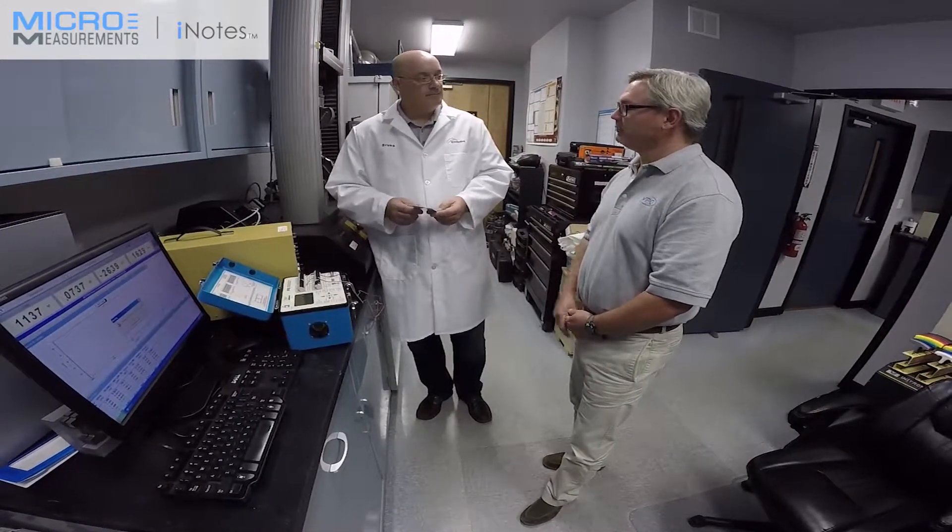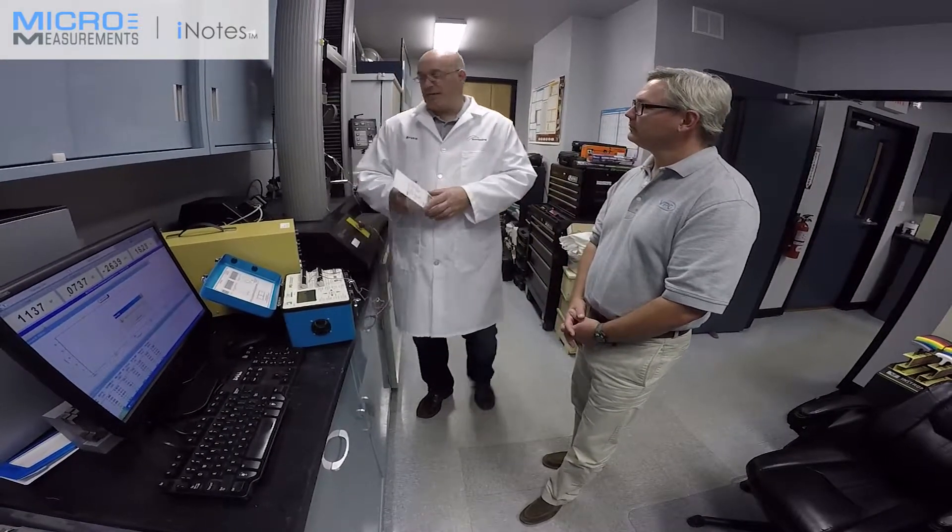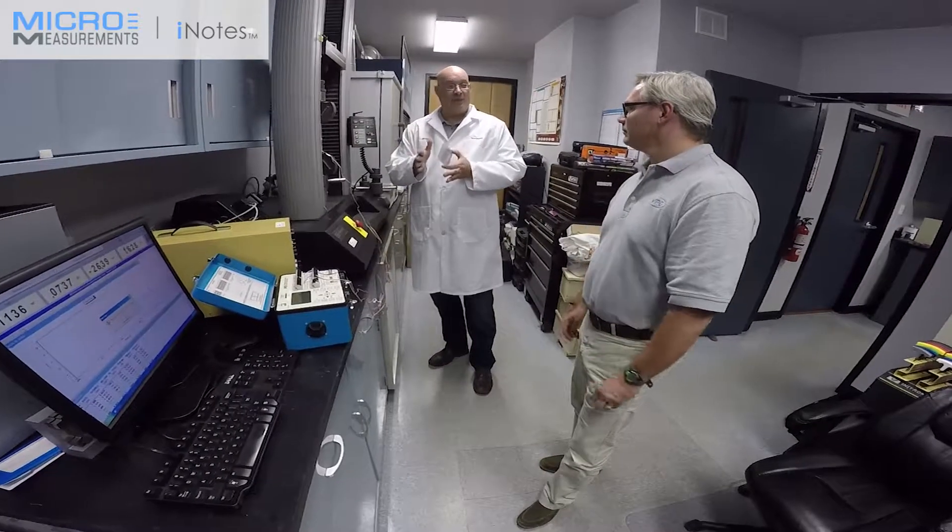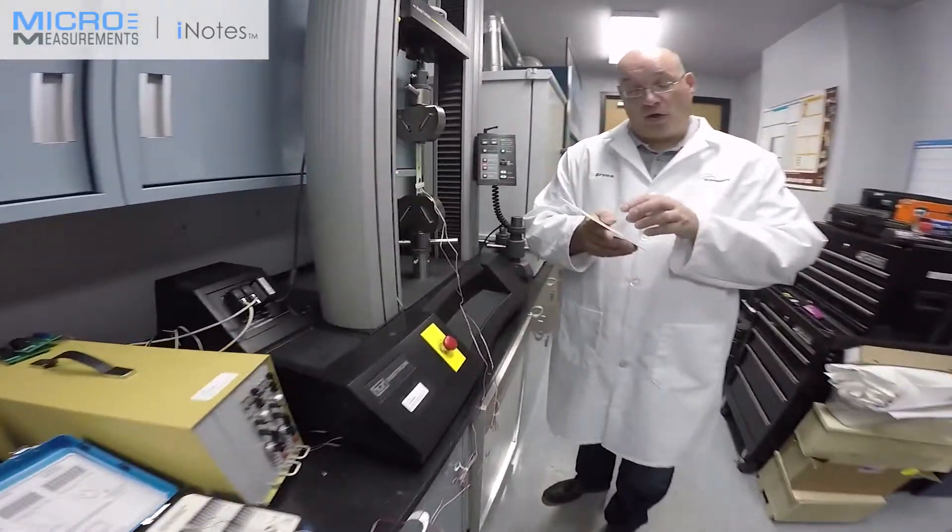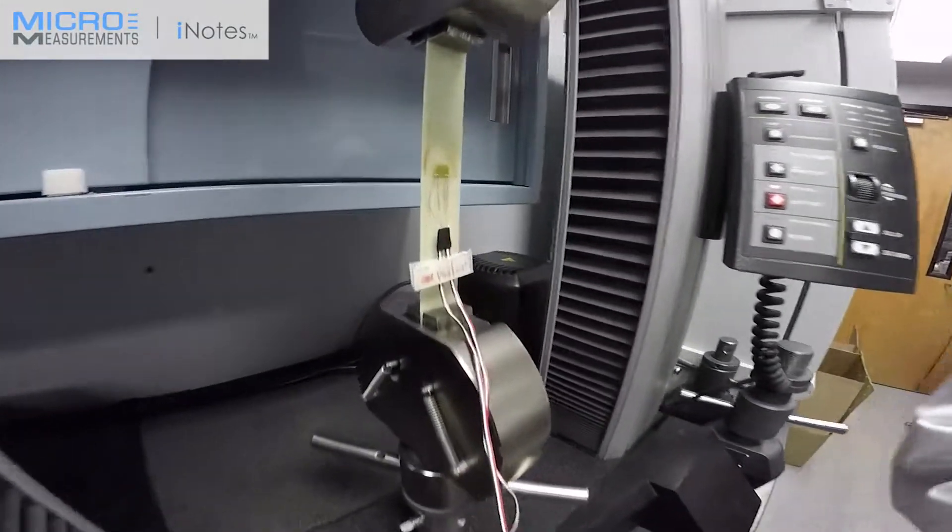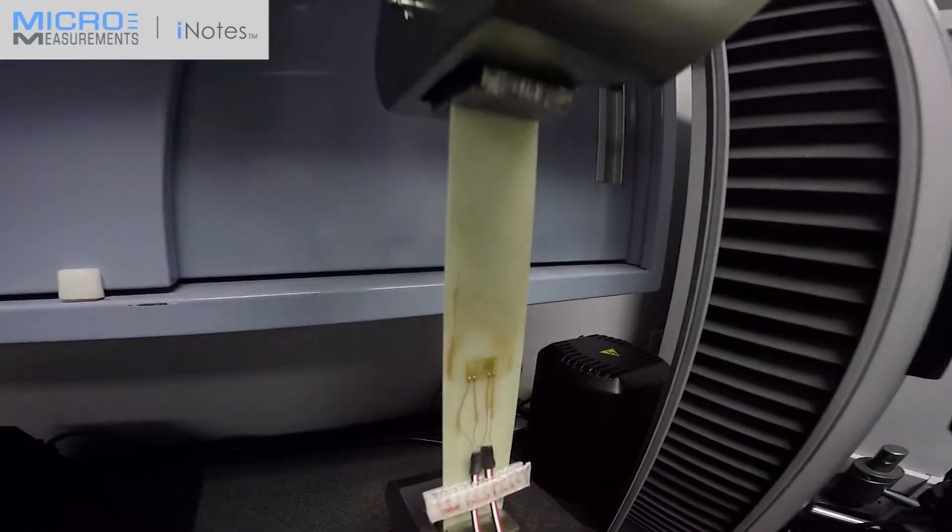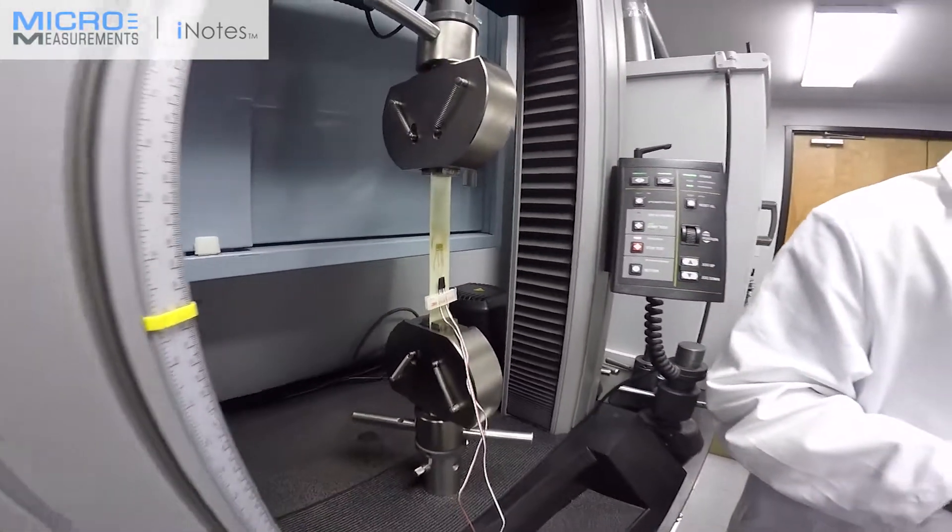So 125 would be an eighth of an inch active gauge length. Correct. Normally, for specimen, with this specimen here, we have a really tight knit fabric, which is perfect to use 125. If you have a bigger fabric or bigger type fiberglass setup, you would use a 250. So you have a better orientation and distribution on the width of the specimen so that you have, you know, accurate data.